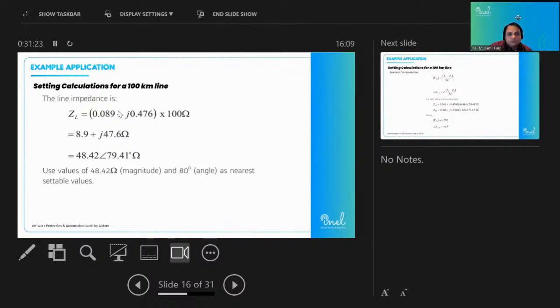So this is the line impedance. We are multiplying it by 100, and these are the values after multiplication. And now this is the conversion from our RX values to impedance and angle values. This is called the line angle, and it is calculated as tan inverse of 47.6 divided by 8.9. So this angle will be there, and this 48.42 is calculated as the square root of R squared plus X squared. So this is the impedance of the line, and we will consider the nearest value for the line angle. Like if this is 79, or even 78, we can consider it as an 80-degree angle.